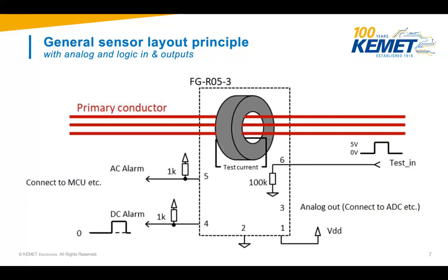If you're not at zero, but shifting a little bit around the lower milliamps, then the power electronics can already foresee that there might be, especially when it becomes wet outside or something like this, that the level could increase. However, this will not trigger an alarm. The alarms are clearly identified, and they are digital signals for AC and DC alarms. And we also have a logic or digital input for a test.